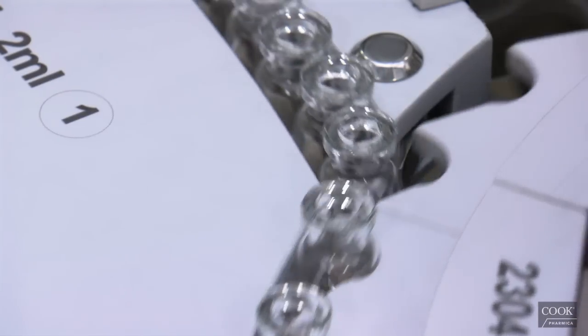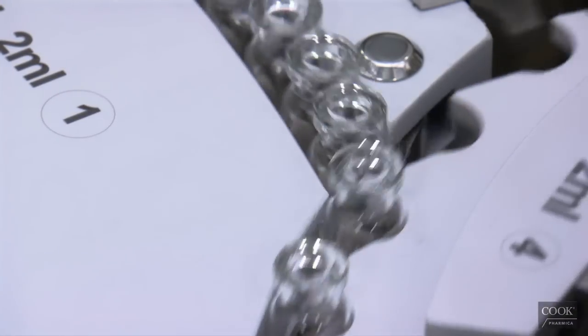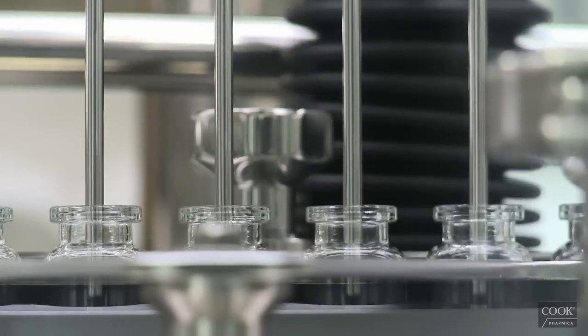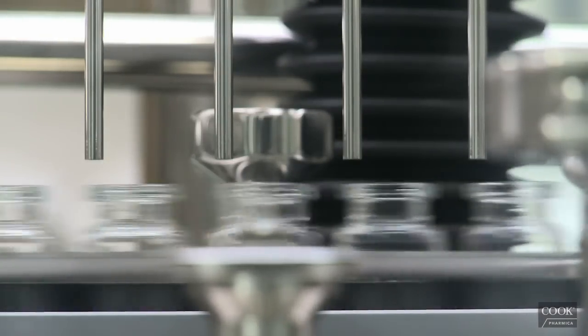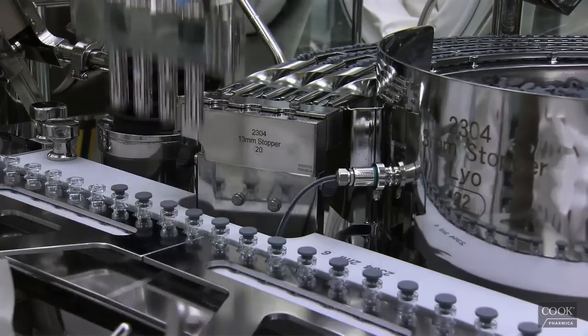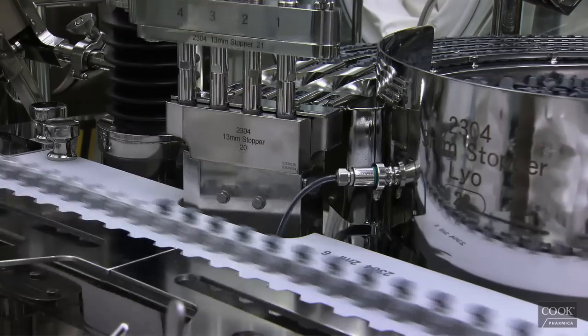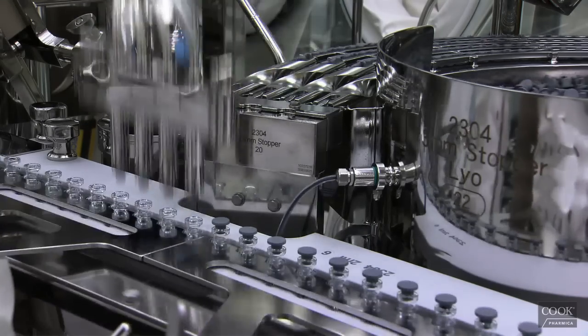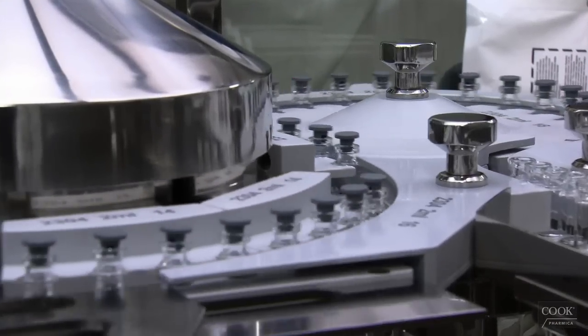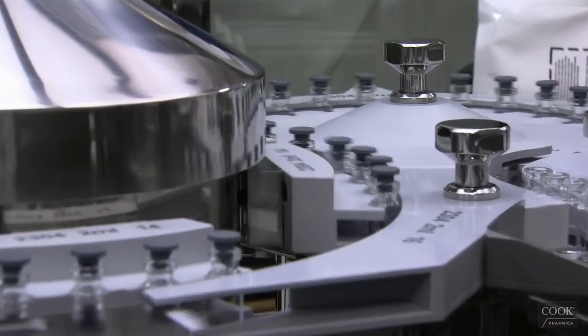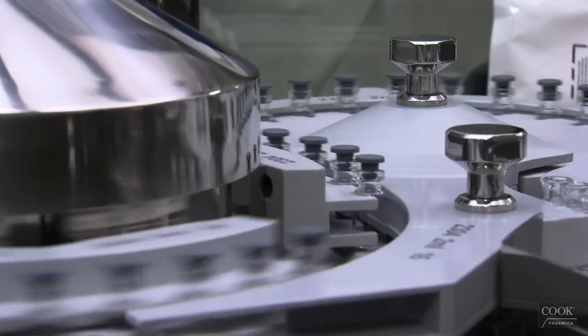The vials are then fed into a four-headed filler which is capable of running up to 150 vials per minute using a time pressure filling mechanism and incorporating 100% non-destructive fill weight checks. A nitrogen overlay can also be provided before, during, or after filling for oxygen-sensitive products.